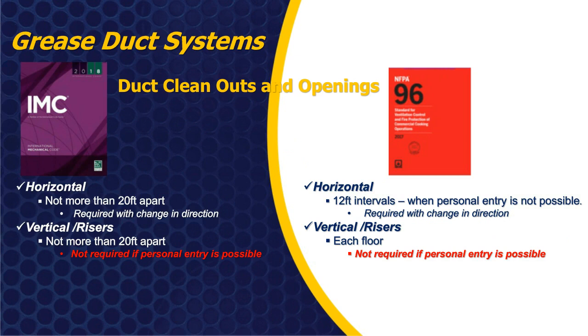Clean out openings. These are going to be critical. Hopefully the systems are going to be going through inspection and cleaning. International Mechanical Code and NFPA are going to have different requirements for clean out access doors. International Mechanical Code is basically going to state that on a horizontal grease duct run, the clean out locations can't be more than 20 feet apart, and they're going to be required in changes of direction to make sure they can access those corners. Vertical risers, again, are going to basically state not more than 20 feet apart. And there's going to be a note in there about not required when personal entry is possible.